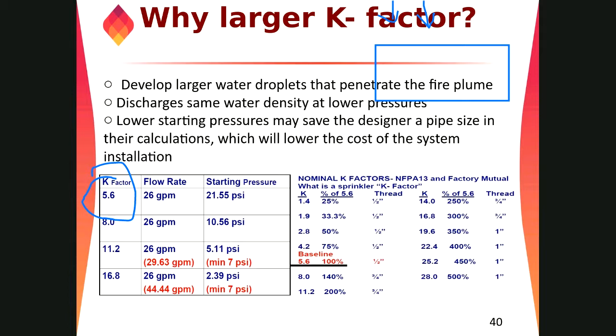What will happen? All the water coming onto the fire, in between the middle, will convert to steam or vapor and go off like steam, because the quantity of heat is so much in kilowatts that small water cannot fight that. So we need a high quantity of water for those fires, like ESFR sprinklers or CMDA or CMSA, starting from 11.2. So the higher the K factor, the higher the water requirement.